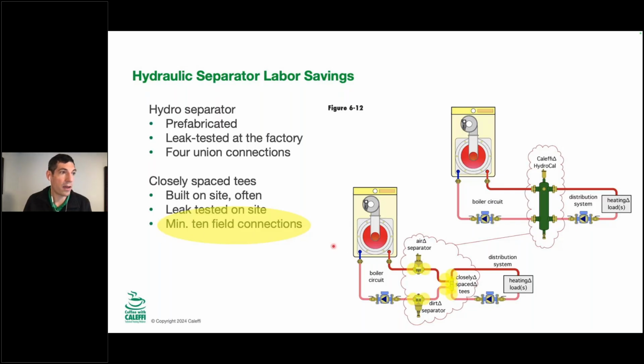But look at the labor rate. To know the true cost of the install here, it could be wildly more expensive depending on the labor to do 10 field connections than it would be to just buy the pre-assembled hydro separator from the shelf and toss it on the wall with a mounting bracket. So again, I'll do my best to not play favorites here, but that is a consideration. If somebody can do this for $10 an hour, go for it. If your labor is more expensive than that, which I assume that it is, it starts to change the equation a little bit.